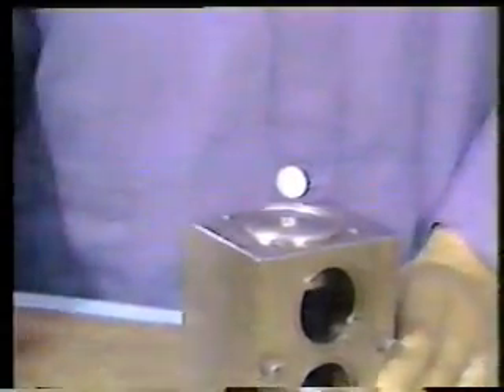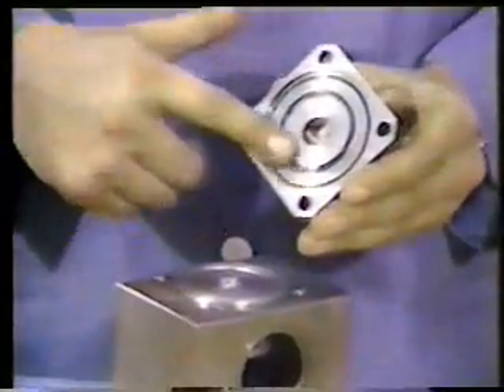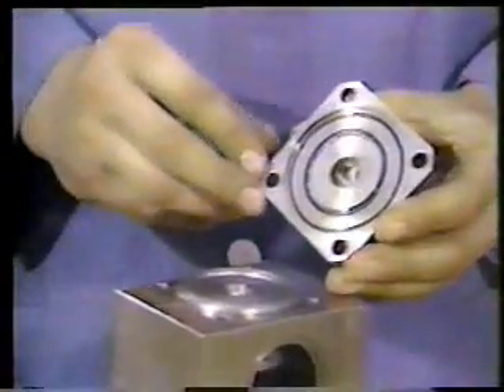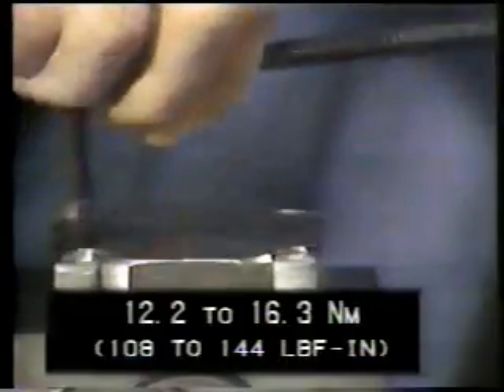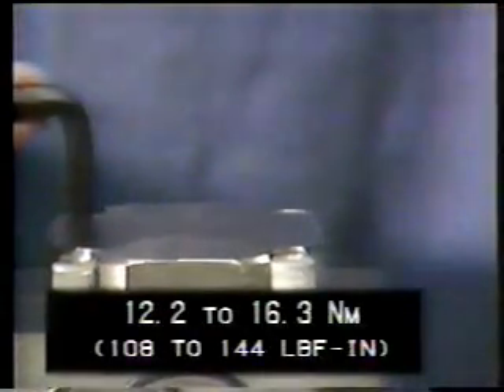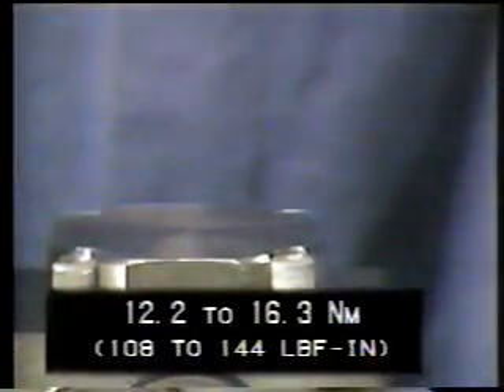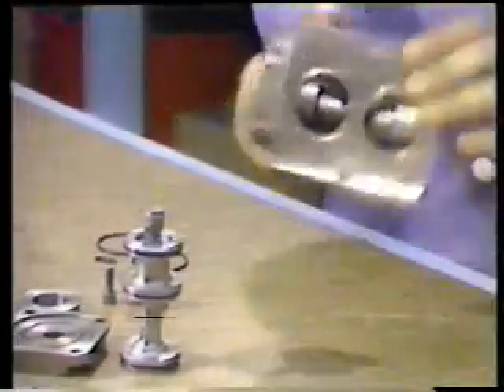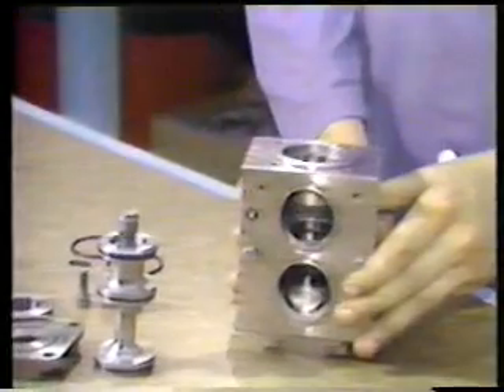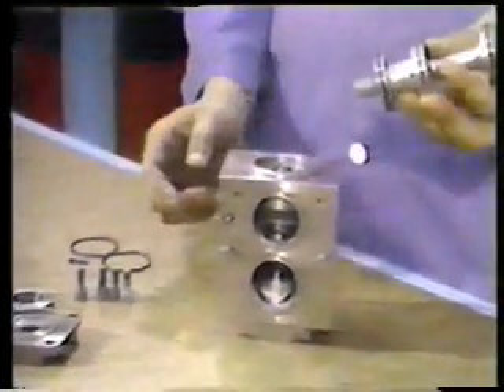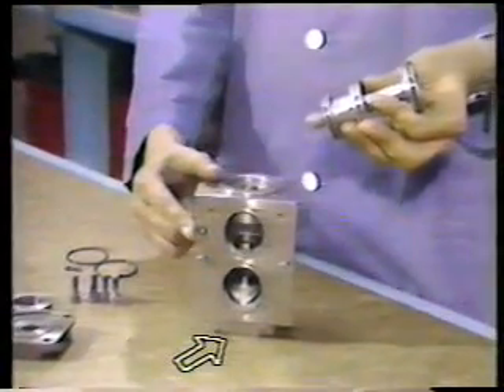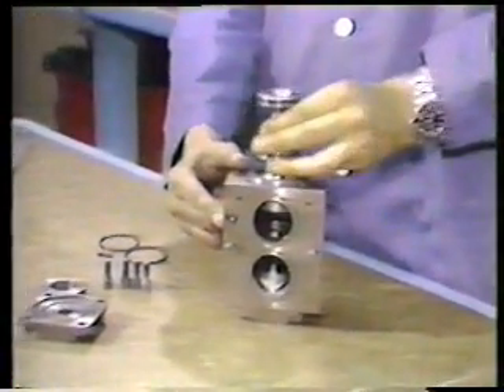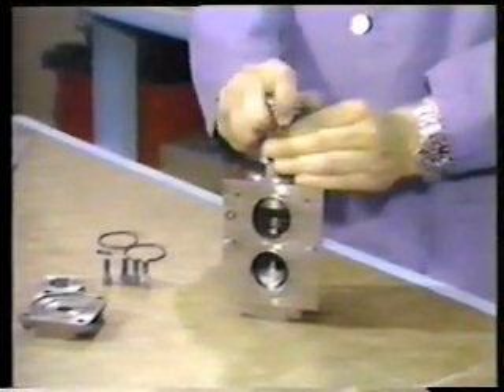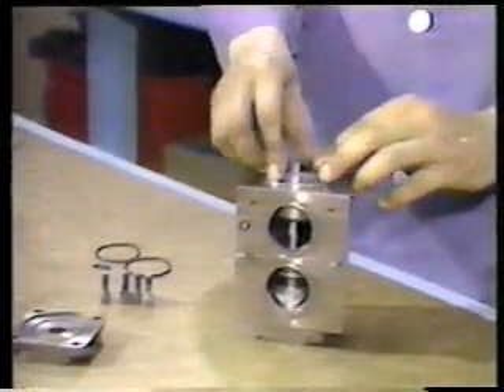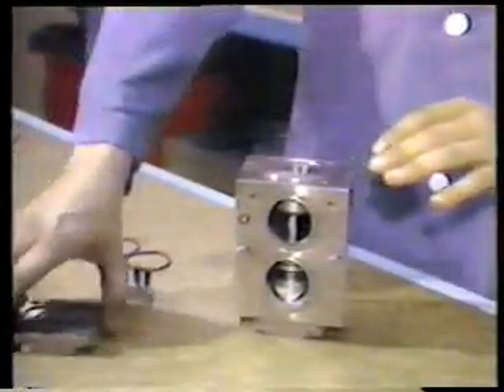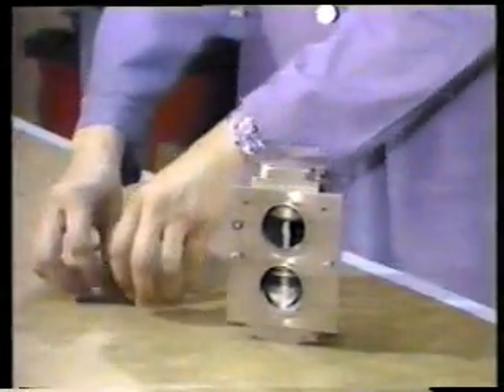And last, install the end cap with the lubricated O-rings in place. Install the 4 bolts and torque to 12.2 to 16.3 Newton meters, or 108 to 144 inch-pounds. Invert the valve body to install the plunger. Note that the detent cage is at the bottom of the valve and the index pinhole is at the top. Carefully work the plunger into the assembly. Next, install the spacer. Install the end cap and 4 bolts.